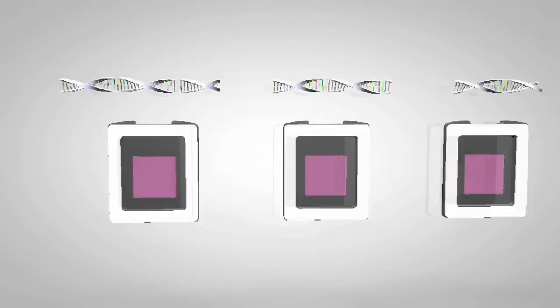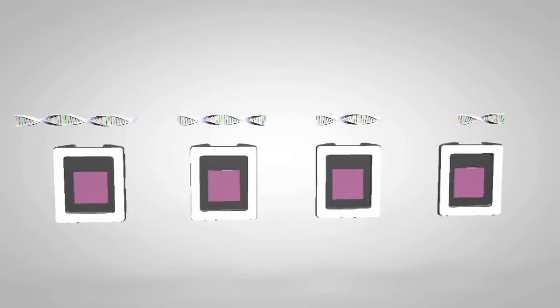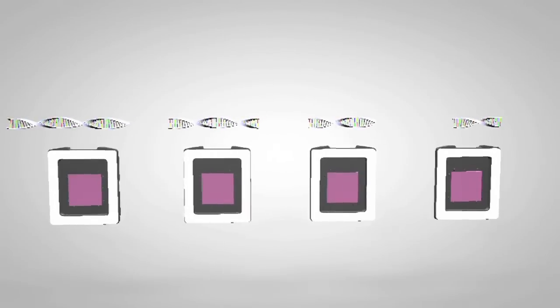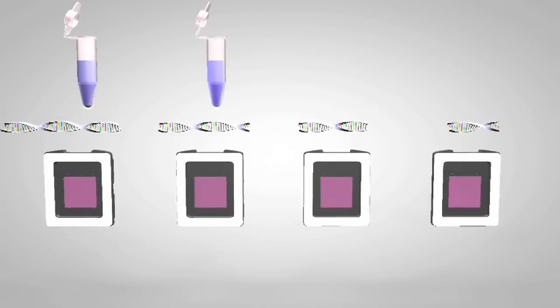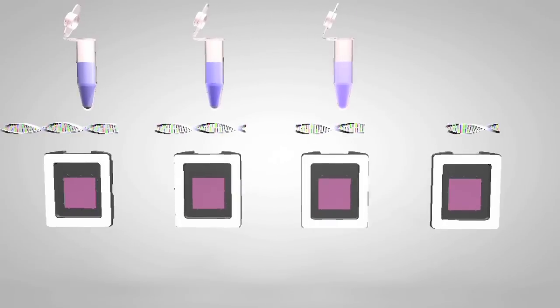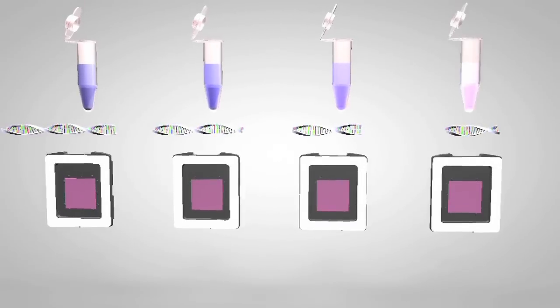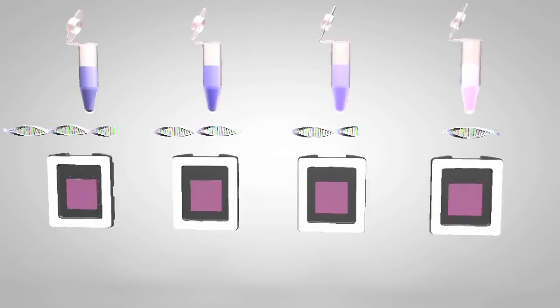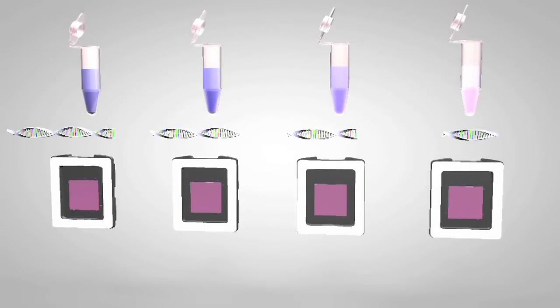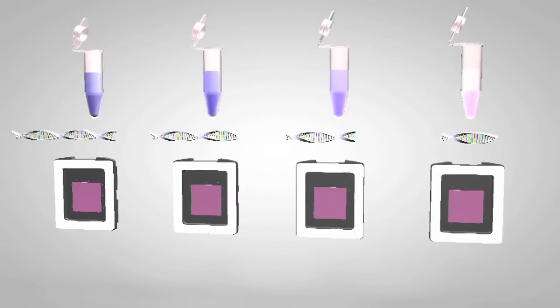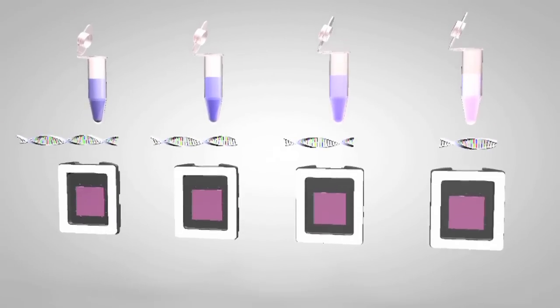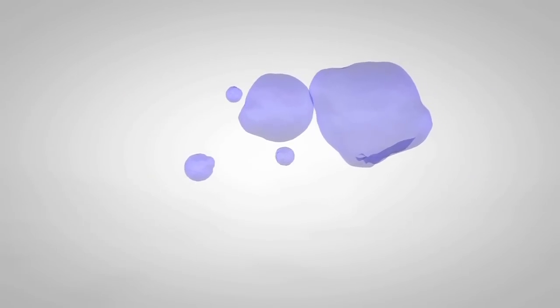This leads to more precise sample loading and less reaction dropout compared to droplet based approaches. And because the chip structure is rigid, the partition reaction volumes remain fixed, meaning you can easily work with samples of varying DNA length and concentration without greatly affecting sample viscosity. This approach eliminates possible additional sample manipulations and extra workflow steps that would be required to normalize viscosities in droplet based technologies.